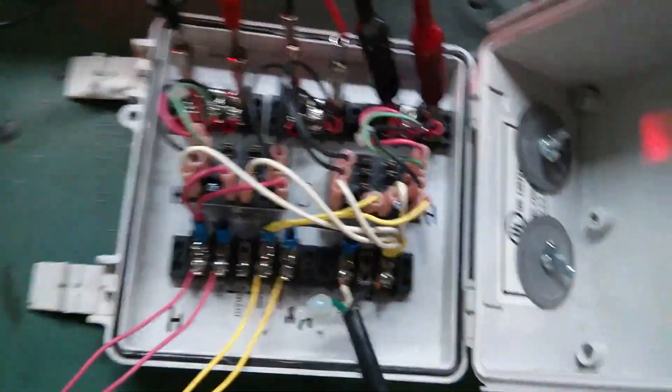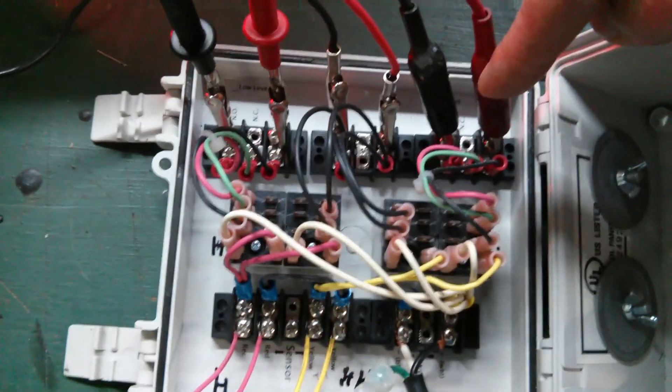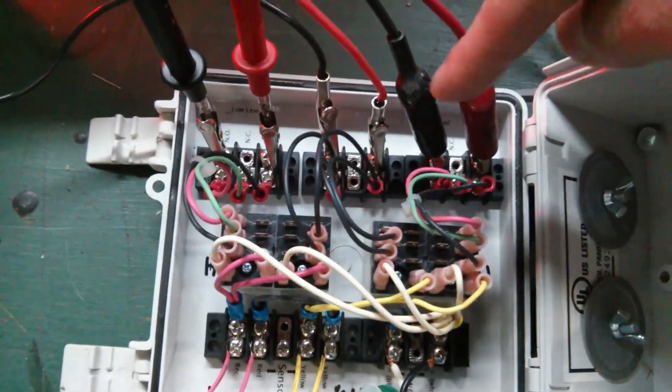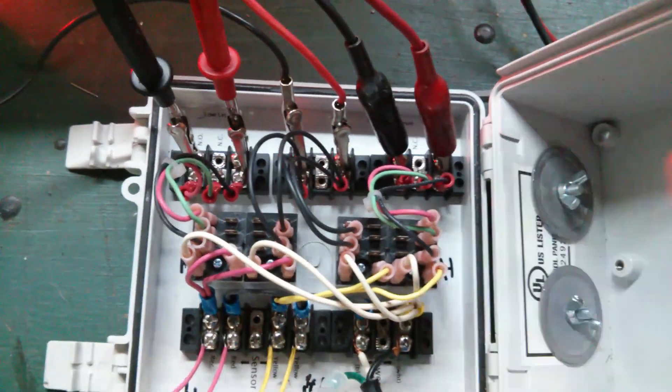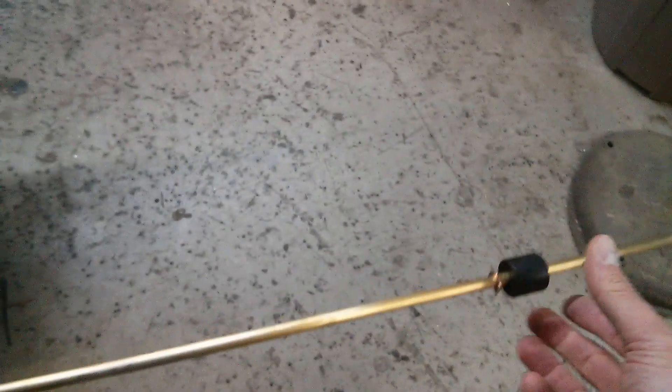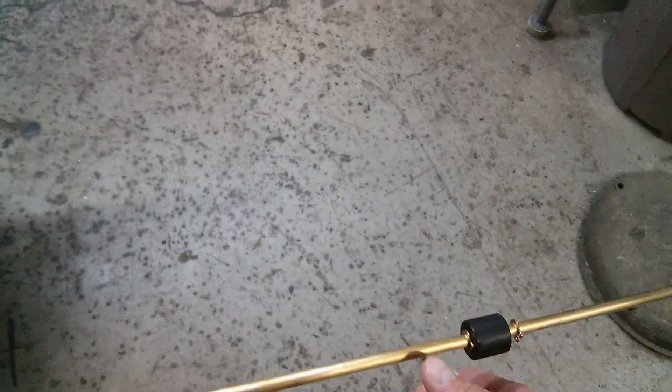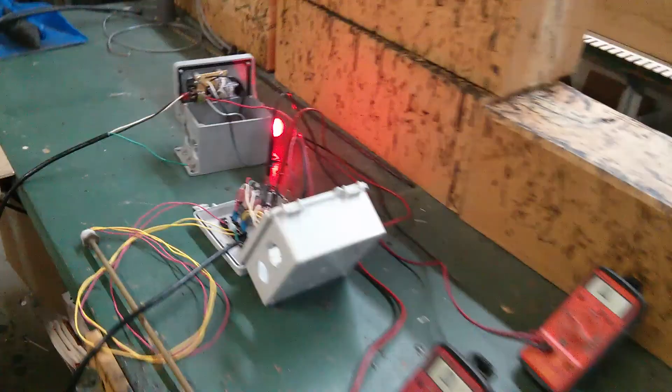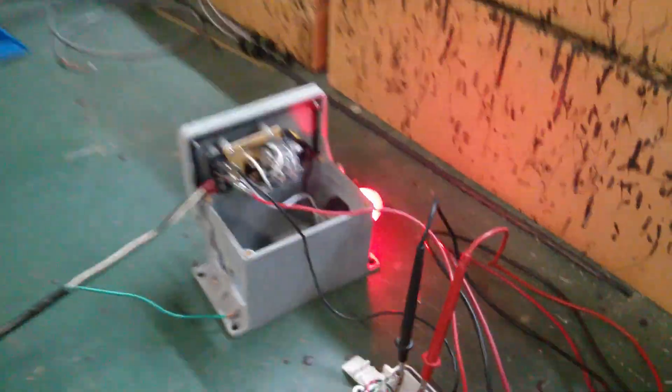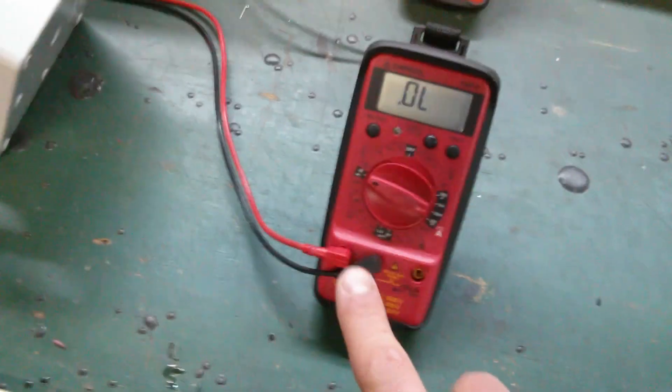So that's your high level relay output right here. High level open, close, open, close as you move the float up or down. I have the alarm silenced, that's why we don't hear that. Demonstrate the low level.